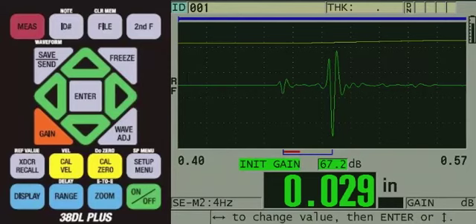At this point, the user should calibrate using samples of known thickness. For best accuracy, they would calibrate using 2 samples of the same material with known thicknesses, representing their minimum and maximum thickness. Once this is completed, we would recommend saving a custom setup.